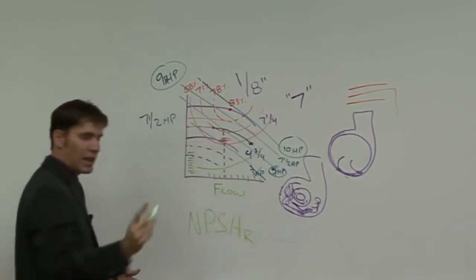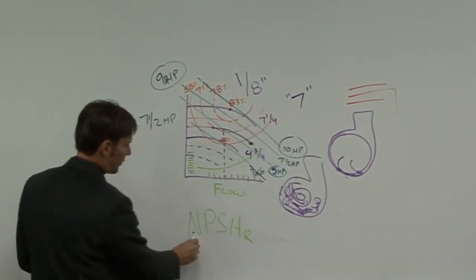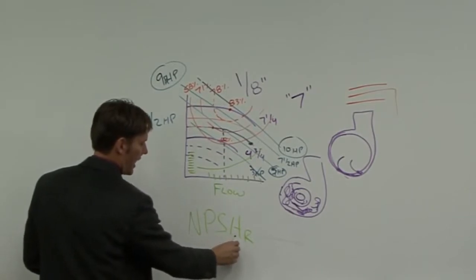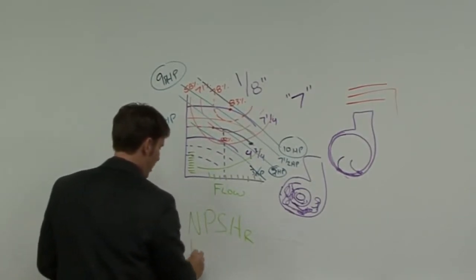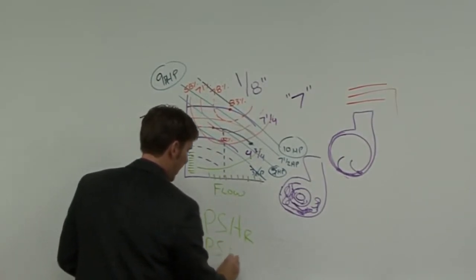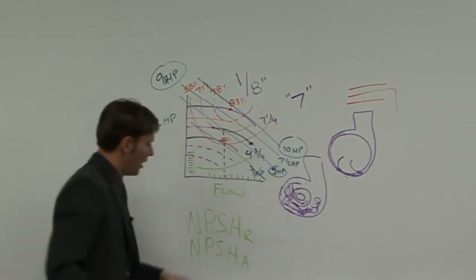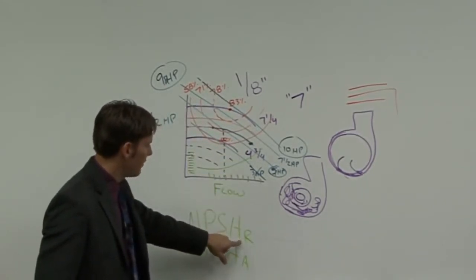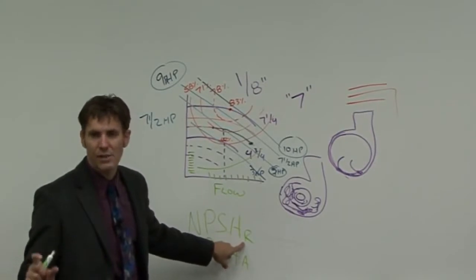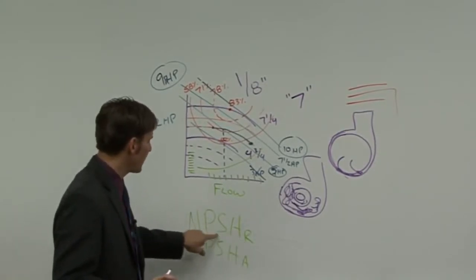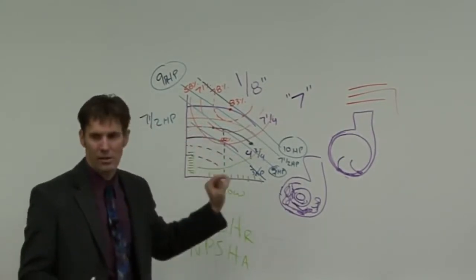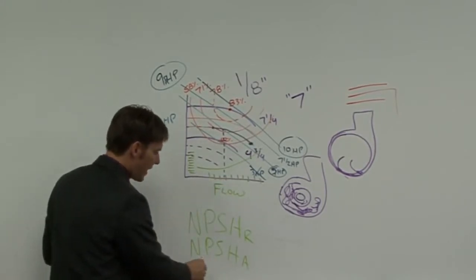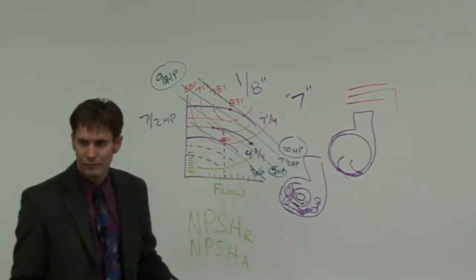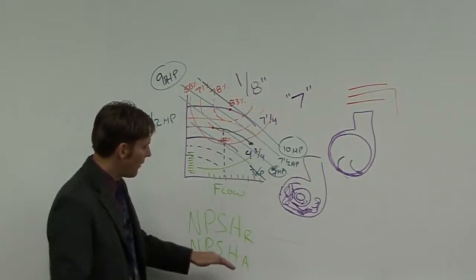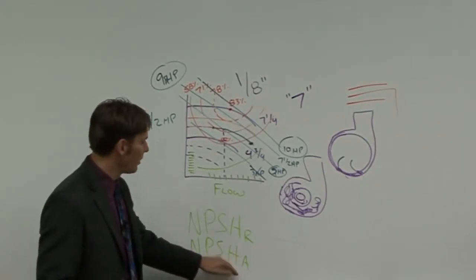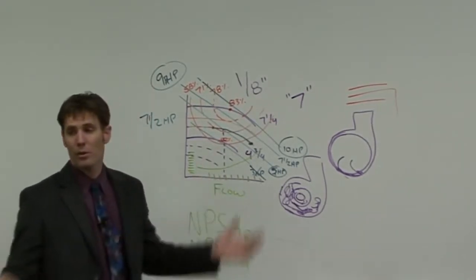NPSH-R. There's 2 types of NPSH. This stands for net positive suction head. My NPSH-R and my NPSH-A. The pump curves will show you the NPSH-R. The R stands for required. My net positive suction head that the pump requires. This is the net positive suction head that's available. If I have more suction head available than what I'm requiring, then my water won't boil.